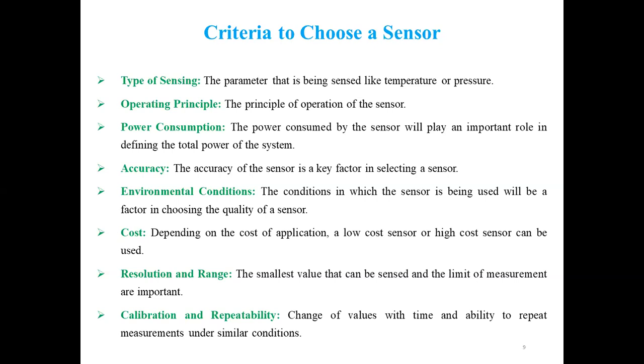If you quote around 2 crores for a small scale industry, they cannot afford it. Even for measuring temperature, they may not give a 2 or 3 crore budget for installation. That's why when selecting a sensor, we should concentrate on its cost, because in the laboratory we may test with one sensor, but when installing the same kind of sensors at multiple locations in industry, we should definitely consider the cost, since as the number of nodes increases, the cost of the entire monitoring system also increases. In such cases, most private industries may not encourage installation or give the chance to install the sensor. So we should also concentrate on the cost of the sensor.